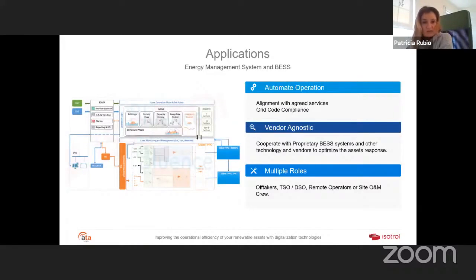And regarding the EMS that we mentioned earlier, the energy management system applied to a battery storage solution. So the main difference for the energy management system is that it's a service or an application that is often embedded in the plant SCADA, and it may share the plant SCADA database. So it does not require a standalone installation such as what I mentioned before for the master PPC. It is also placed at a higher level in the plant hierarchy for control.